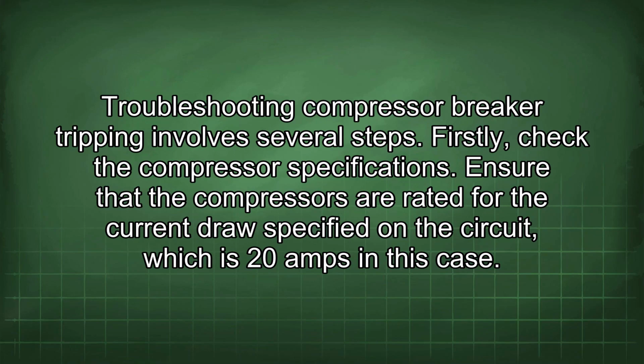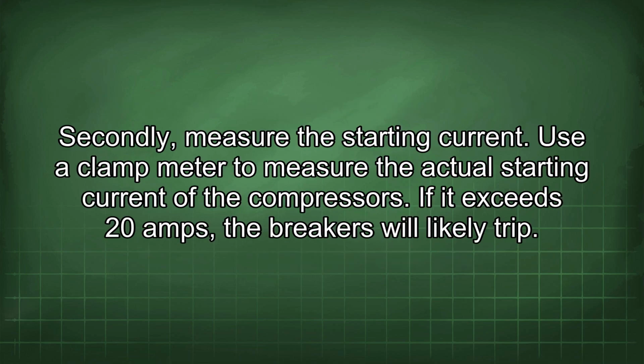Troubleshooting compressor breaker tripping involves several steps. Firstly, check the compressor specifications. Ensure that the compressors are rated for the current draw specified on the circuit, which is 20 amps in this case. Secondly, measure the starting current. Use a clamp meter to measure the actual starting current of the compressors. If it exceeds 20 amps, the breakers will likely trip.